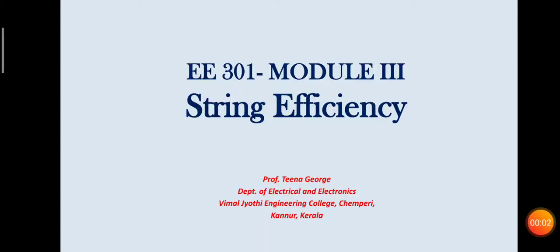Hello everyone. In transmission line insulators with higher voltages, we are using suspension insulators with a number of discs. To increase the voltage level, the number of discs can be increased. But while using suspension type insulators, the voltage distribution across each disc or each string will be different. That is due to the shunt capacitance present between the insulator disc and the tower.